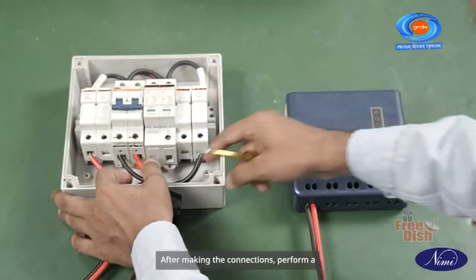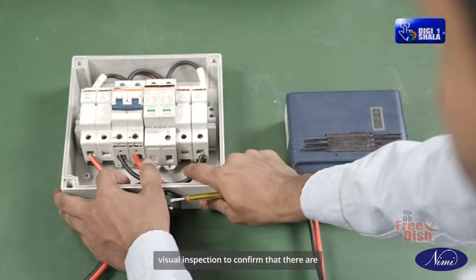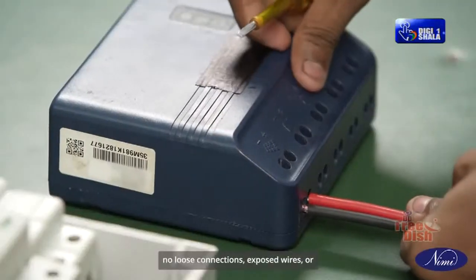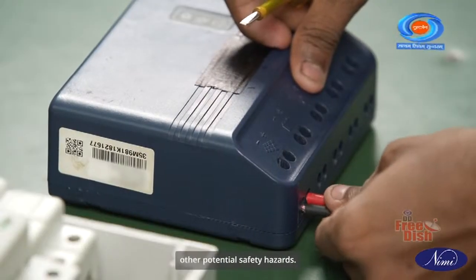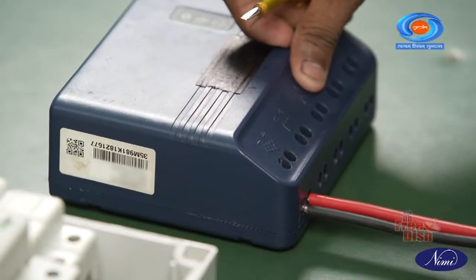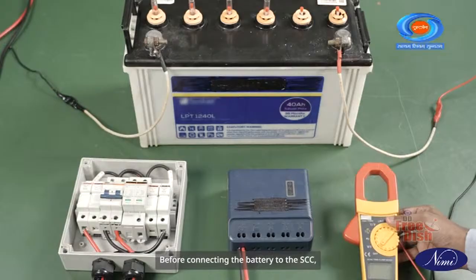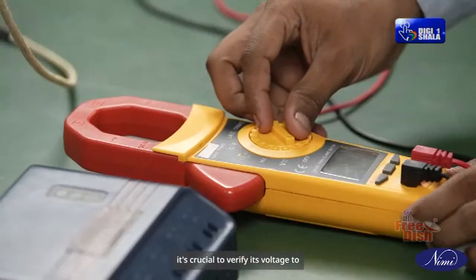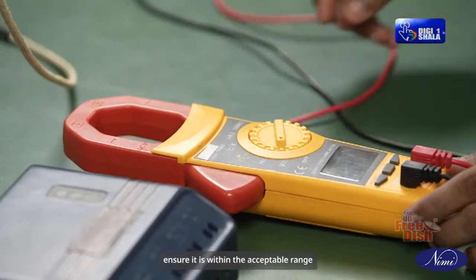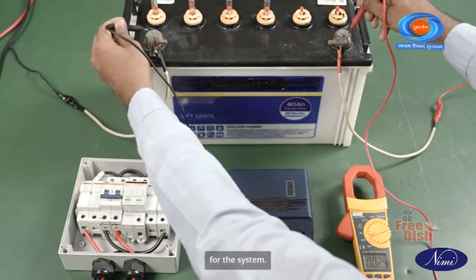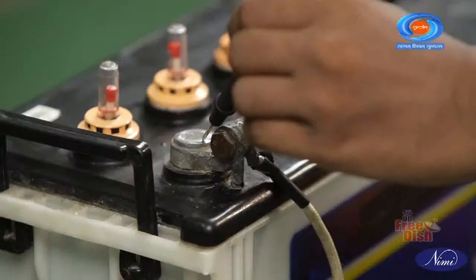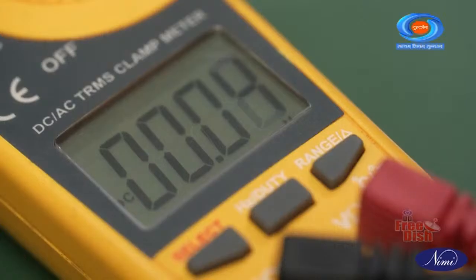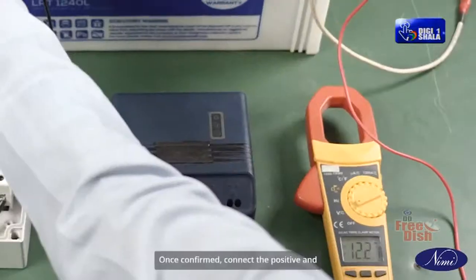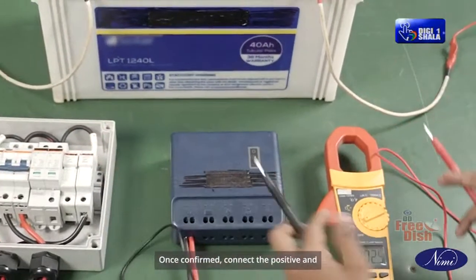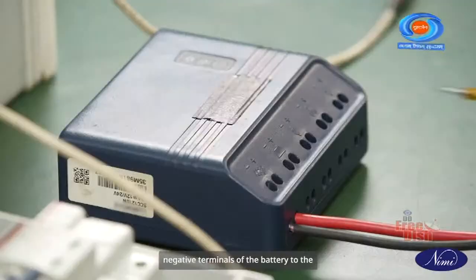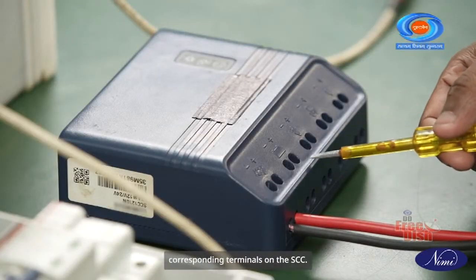After making the connections, perform a visual inspection to confirm that there are no loose connections, exposed wires, or other potential safety hazards. Before connecting the battery to the SCC, it is crucial to verify its voltage to ensure it is within the acceptable range for the system. Once confirmed, connect the positive and negative terminals of the battery to the corresponding terminals on the SCC.